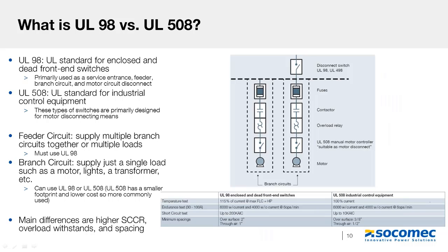So to summarize, the UL98 standard is for enclosed dead front switches, while the UL508 is the standard for industrial control equipment. The UL98 switches have higher short circuit ratings, and they can be used for service entrance, feeder, branch circuit, or motor disconnection. If you have a motor application with a high circuit rating, you can use the UL98 switch for that. The UL98 also has higher overload withstand and requires more spacing than the UL508 switches. So you can see the UL98 switches in the coming slides. They're a little bit bigger because of these different requirements from the standard.